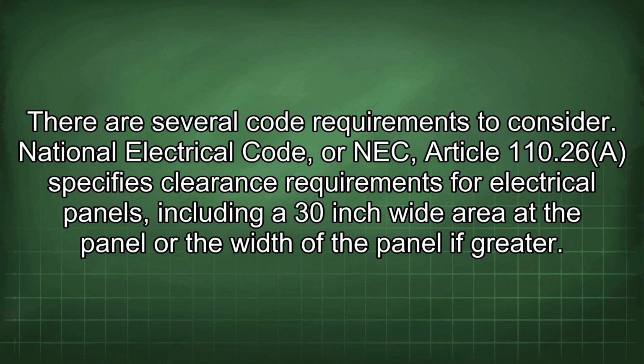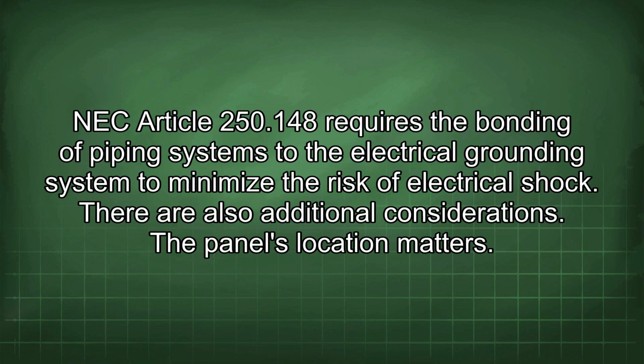There are several code requirements to consider. National Electrical Code, or NEC, Article 110.26 specifies clearance requirements for electrical panels, including a 30-inch wide area of the panel or the width of the panel if greater. NEC Article 250.148 requires the bonding of piping systems to the electrical grounding system to minimize the risk of electrical shock.